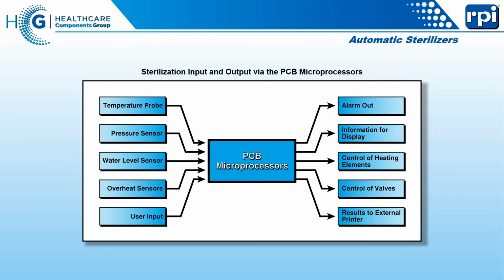What do we want to get out of these machines? Well, we have to be told if there's an alarm. We want to know what the machine is doing, how it's doing it, how it's getting the water in and out, and if possible, get some results so you have record keeping of what that machine actually did. Now, this one down here, results to external printer, is kind of in development because a lot of machines, instead of an external printer, use a data logger, an external system that puts the cycle information onto a memory stick or memory disk of some sort, and it's usually loaded somewhere like a Google Doc or somewhere on the cloud, and that's where your record keeping is. No more little pieces of paper.